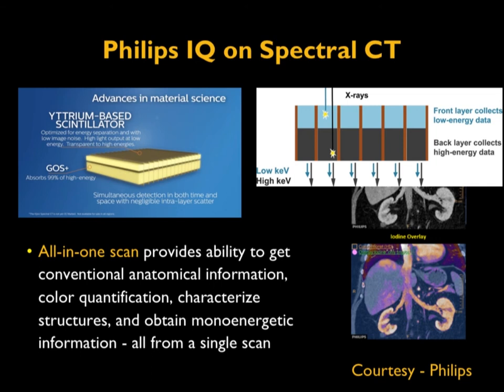The advantage of this approach is that it is an all-in-one scan, providing the ability to conveniently obtain conventional anatomical information and color-coded data in a single scan. Instead of a single-layer detector, a dual-layer detector separates the x-ray spectrum into low and high energy, which can be combined together to reconstruct monoenergetic x-ray images.